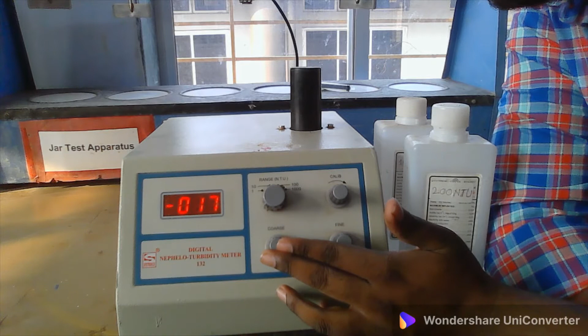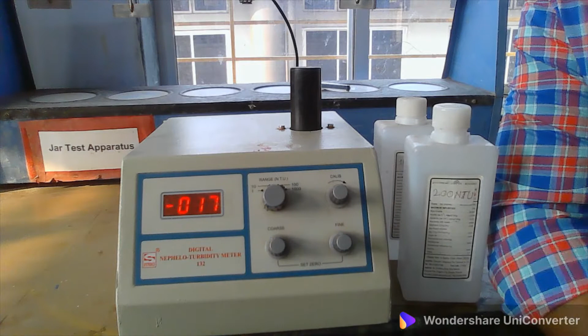Then the third knob is also a calibration knob. Here there are two knobs, coarse and fine. Very fine adjustment and calibration we do with the fine knob, and the coarse knob is for larger calibration. If we want calibration in the 0.01 NTU range, we use fine. If the difference is greater than 5 NTU, we use this coarse knob to do the adjustment or calibration. And here we can set 0 for the distilled water. As all of you know, distilled water is free from impurity, and the turbidity of distilled water is 0.